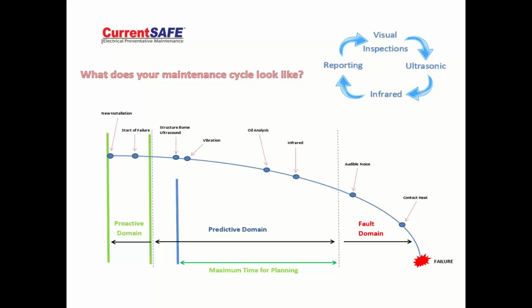This is a predictive maintenance chart. On the left-hand side of the screen, once you energize a component in an electrical distribution system, you start its life expectancy span. From the time it's energized to the time it fails is a given set time. The earlier we can detect an anomaly, the more we can extend that maximum time in the middle for planning, correction, cleaning, and adjustments. So structure-borne ultrasound is the earliest form of detection.